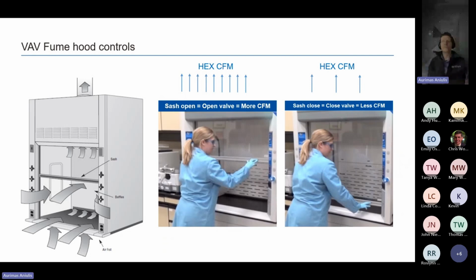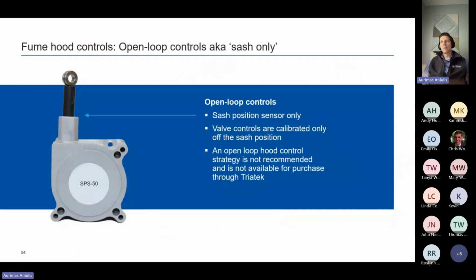And there are 2 modes of operation for fume hoods. There's the constant volume, and then there's the variable air volume fume hoods. And that's what we're showing here. On a variable air volume fume hood, as the sash opens, more CFM is being exhausted. As the sash closes, less CFM is being exhausted. Pretty basic stuff. Well, let's keep going and see how far that holds.